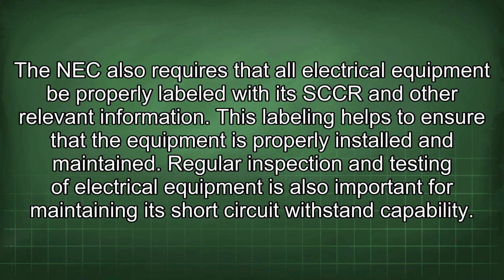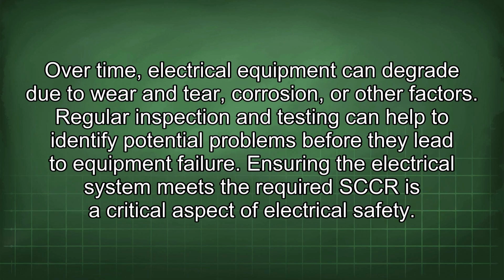The NEC also requires that all electrical equipment be properly labeled with its SCCR and other relevant information. This labeling helps to ensure that the equipment is properly installed and maintained. Regular inspection and testing of electrical equipment is also important for maintaining its short-circuit withstand capability. Over time, electrical equipment can degrade due to wear and tear, corrosion, or other factors. Regular inspection and testing can help to identify potential problems before they lead to equipment failure.